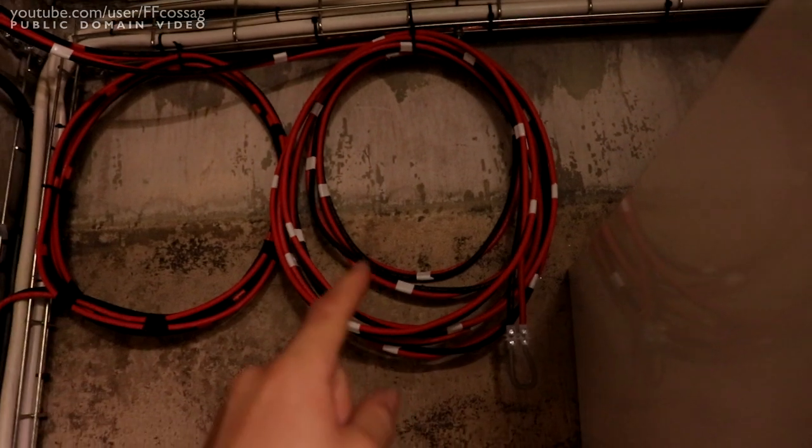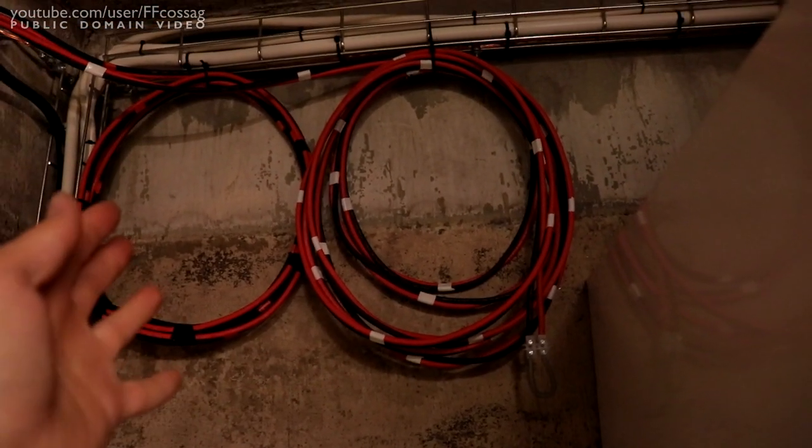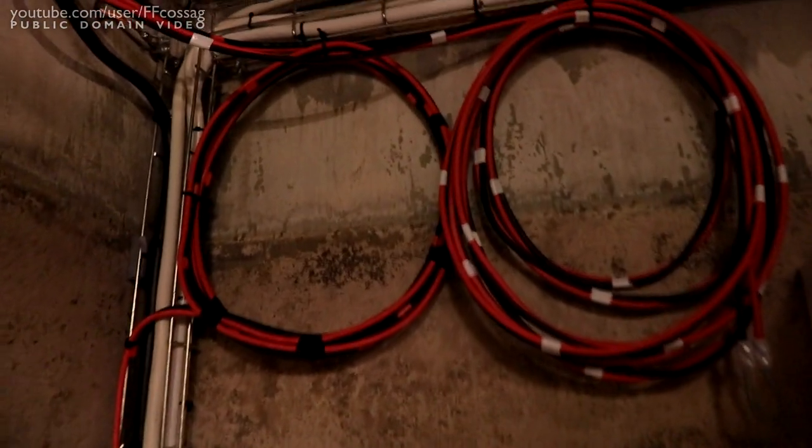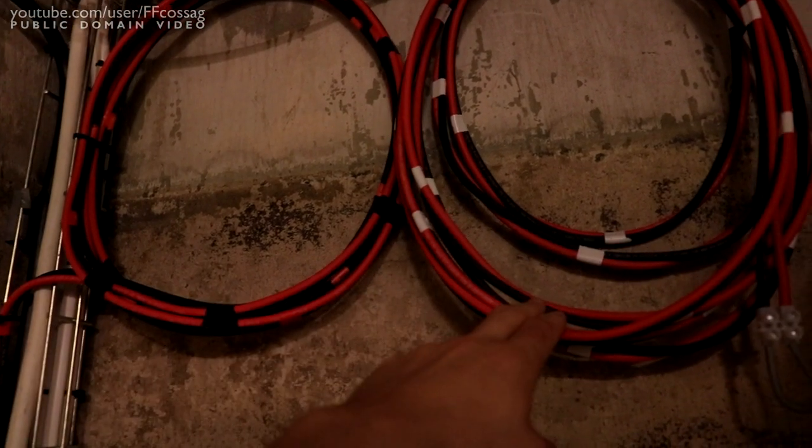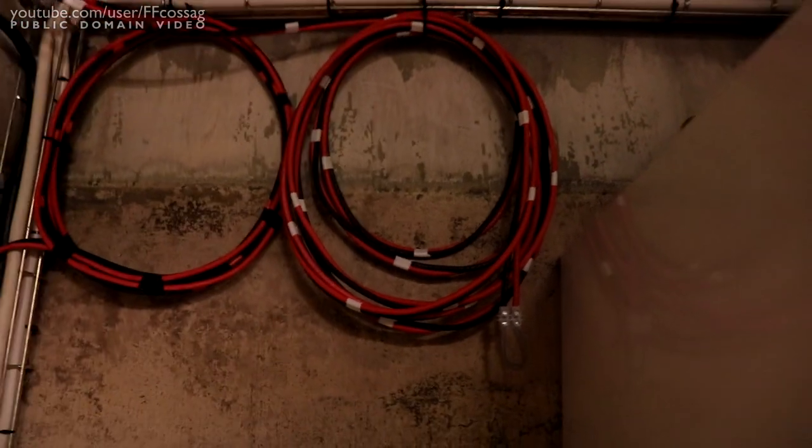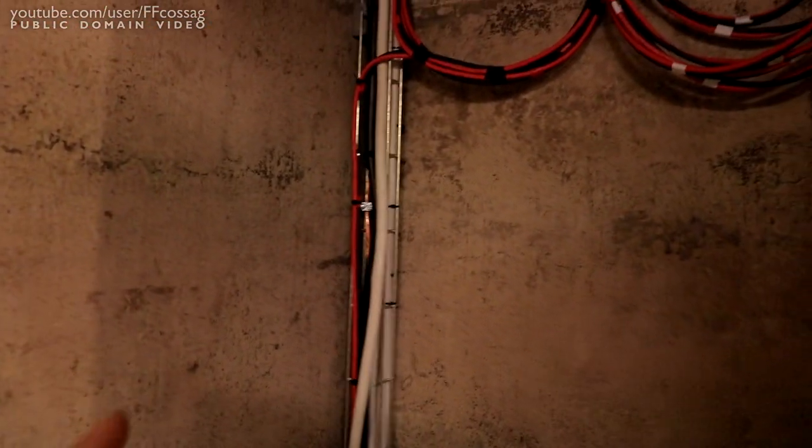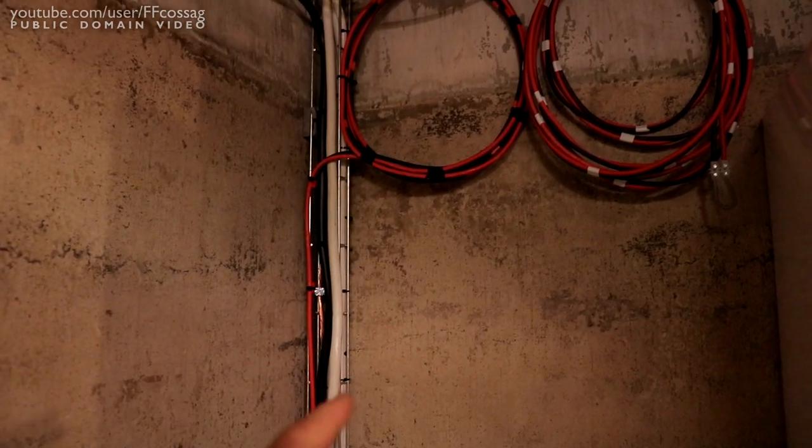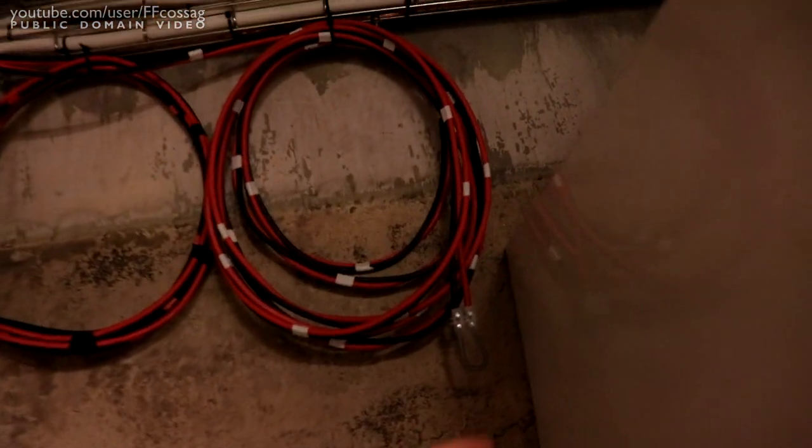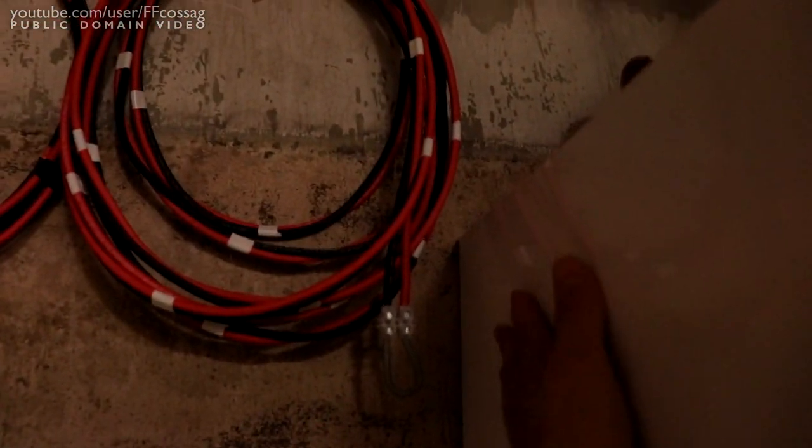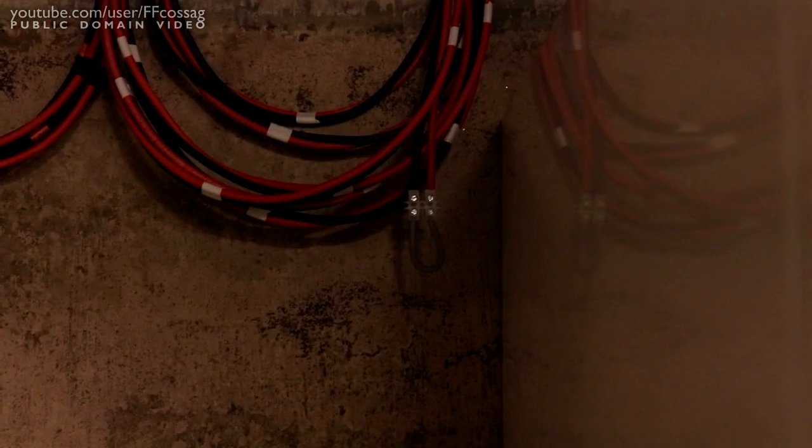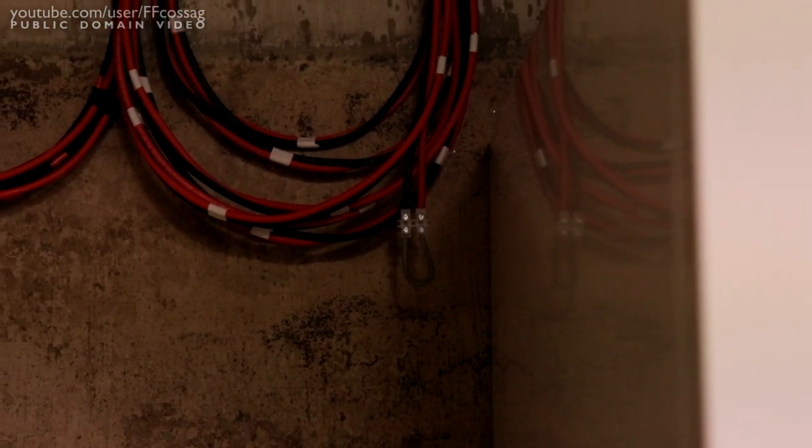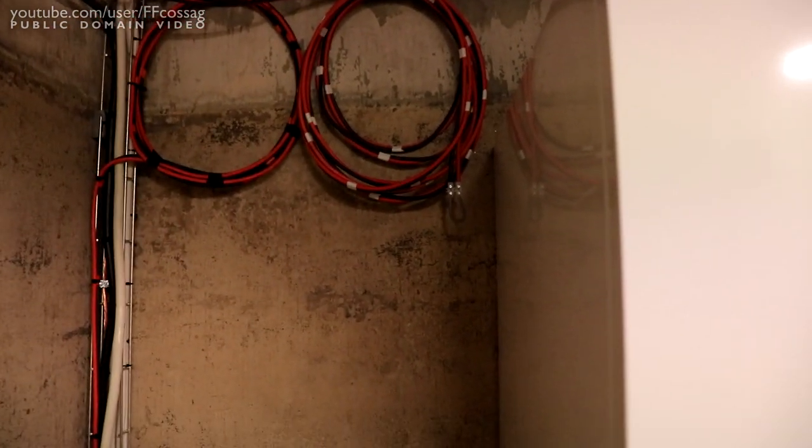Because we need to keep in mind, both of these wires end up in the same switch in the DC box on the barn, and if we have that moisture ingress, we could get 800V DC from this seeping through the switch into this, making these ends absolutely lethal, because the inverter has the negative side of the black and white lead referenced to neutral, which is referenced to ground. So, we could essentially have ground in this metal, ground in that pipe, and 800V in the red lead there, and that is just unacceptable. We cannot have that. So, with a jumper sitting like that, it's guaranteed to be at 0V potential over time.